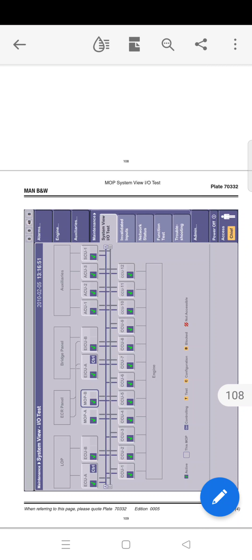When the diode is yellow, the MPC is downloading the software from the hard disk, that is the MOP, or is in the test or configuration mode. So guys, no need to worry about this also, and normally this takes a few minutes. When the diode is red, the MPC is unavailable. That means there is a problem with the MPC.